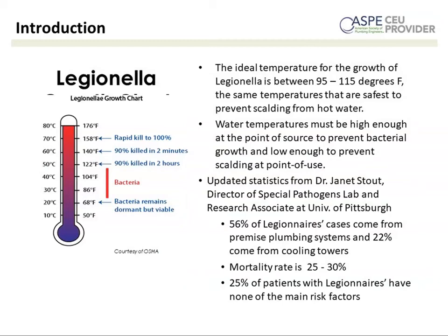You can see many people have seen this chart to the left, which tells you the ideal range and also at what temperatures and how quickly bacteria is killed. When you get up to 158 degrees, that's the rapid kill rate, which is typical of a sanitization or a hot water flush. That's typically the temperature where those occur.